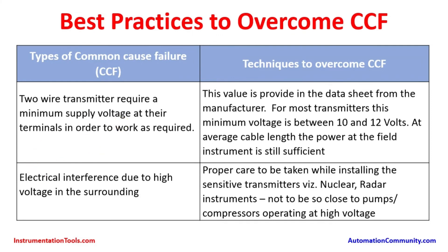Two-wire transmitters require a minimum supply voltage at their terminals to work correctly for pressure, flow, differential pressure, temperature, and level measurements. In some plants, field instruments may be far from the control room, causing the 24 V supply to drop to 15 V or 14 V depending on cable type and length. Where this occurs, step-up voltage devices or additional barriers must be installed in between.